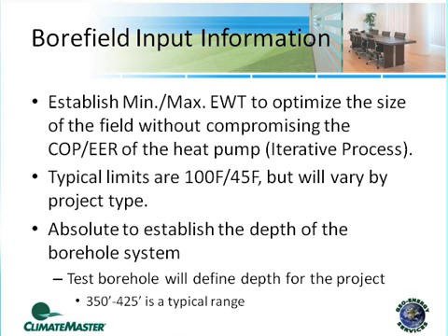Now, on the borefield, here's a couple of things to know on the inputs. We need to know the minimum and maximum water temperature that we're designing to. That's also going to translate to the COP and the EERs of the equipment. So typical limits, and this is going to vary across the United States, are going to be 100F/45F. Honestly, that's just a suggested starting point. You should always look at every project and decide from there, based on iterations, whether you need to massage and relax those limits or constrain those limits some more to balance the size of the borefield, which is going to be related to the installation cost, and also balance the COP and EER of it.